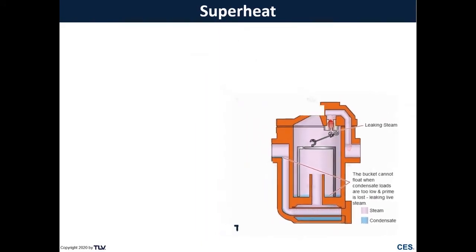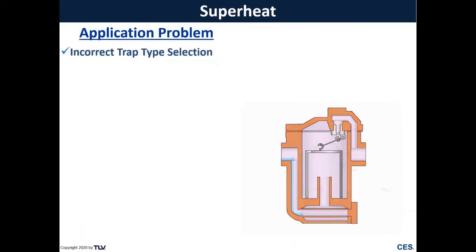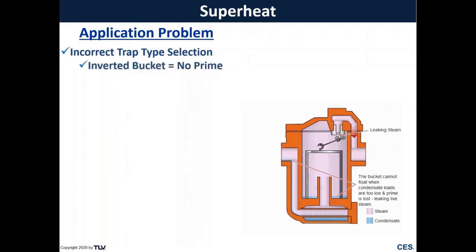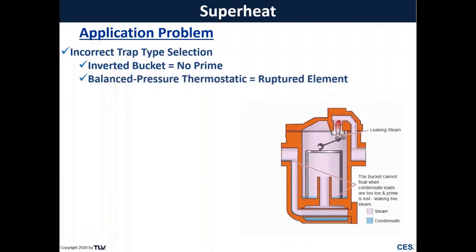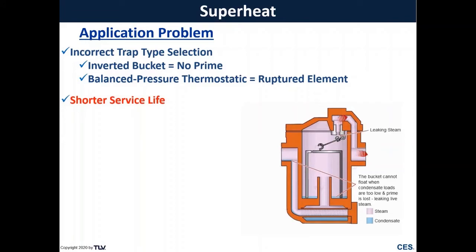Next is superheat — a specific application where steam is at a higher temperature than saturation. Selecting the incorrect trap type can cause issues. For an inverted bucket, superheated steam has a low condensate load, and the extra heat evaporates condensate in the trap, so the bucket won't have prime and can't float up to close, causing the trap to leak through. For a balanced pressure capsule thermostatic trap, the extra heat causes the capsule to overexpand and rupture, failing it open. Superheated steam leaks can also be dangerous because they're invisible — no steam plume.